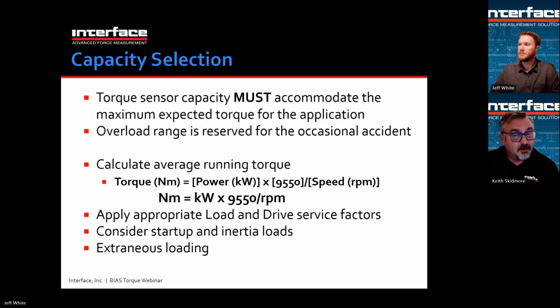Now, under impact loading, not quite so easy. If somebody said, okay, I'm going to hit this load cell with a hammer, what capacity do I need? Surprisingly, you might need a lot higher capacity than you might expect. Same thing with torque. Torque is rotating in a lot of cases, and so you have dynamic conditions to consider. It's not just a simple, this much torque. If you're testing a valve, it might just take a certain amount of torque to turn the valve. That may be easy. But say a motor spinning a compressor, and you're trying to measure how much power that system requires: there's a lot more going on than just applying a constant torque. There are compressor pulses, there are motor pulses as the poles of the motor are spun past. So basically you have to figure out what the capacity needs to be, and torque sensors always have a capacity.